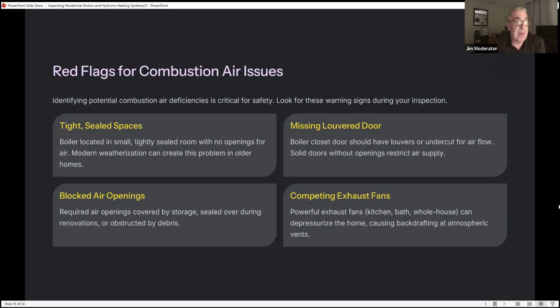Red flags for combustion air issues. Identifying potential combustion air deficiencies is critical for safety. Look for these warning signs during your inspection. Tight, sealed spaces: boilers located in a small, tightly sealed room with no openings for air. Modern weatherization can create this problem in older homes.